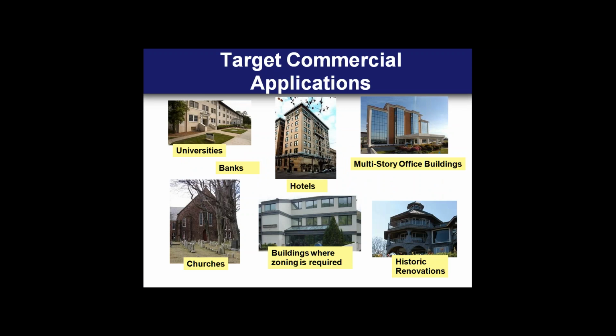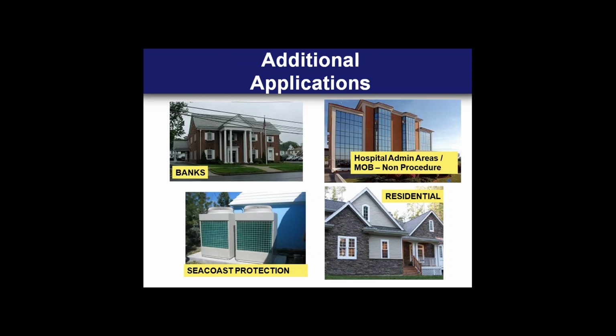In terms of target applications, all of these pictures on this slide represent applications, projects where VRF has been installed successfully and continues to claim greater market share of these common commercial institutional type applications. I think a couple applications to look out for that really aren't suited to VRF is when you're dealing with invasive procedure, classified type clean rooms, classified type laboratories. Because of the decentralized concept around these systems and the low fan power consumption, the indoor units typically don't have significant static pressure capabilities to overcome HEPA filtration. And then certainly in process or caustic type environments, the equipment's really not suited for that. The materials and the coating methods aren't suited to harmful environments like that, so that's something to stay away from.